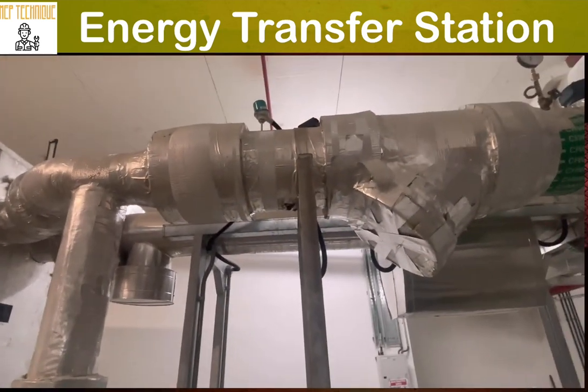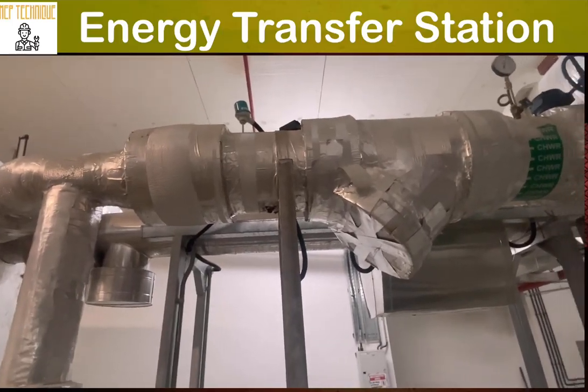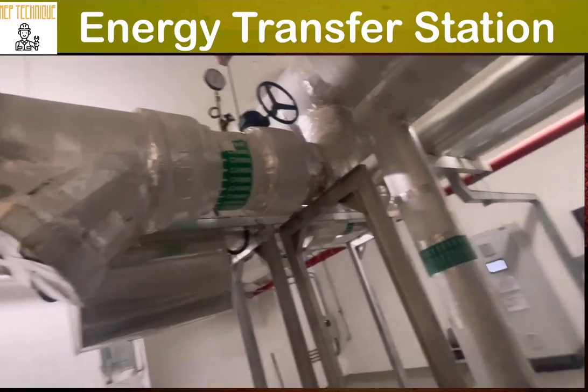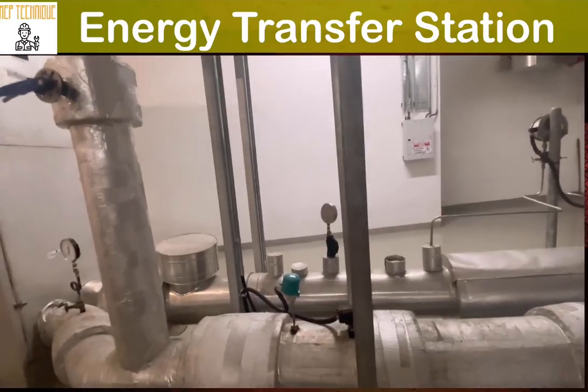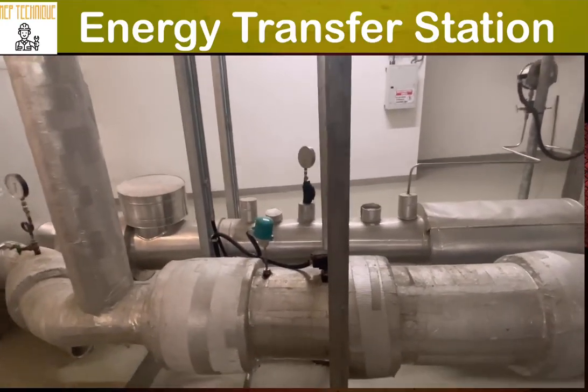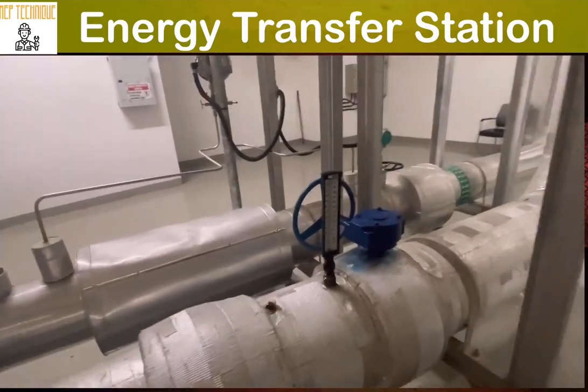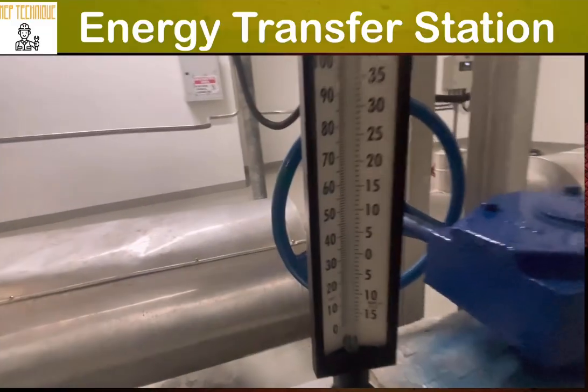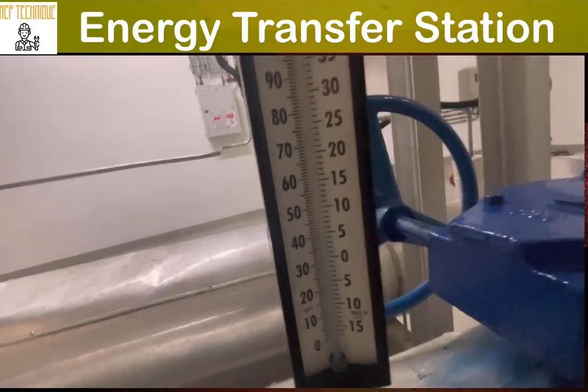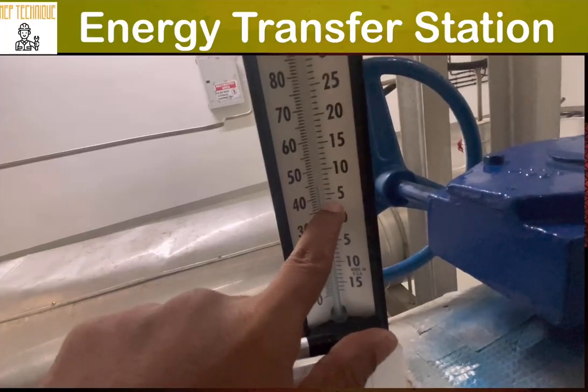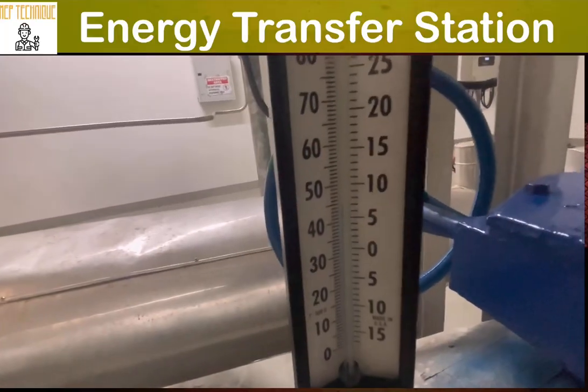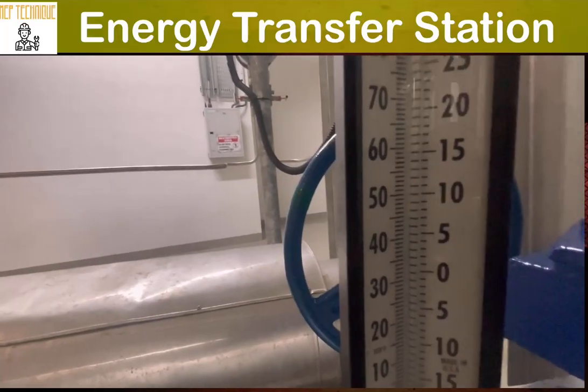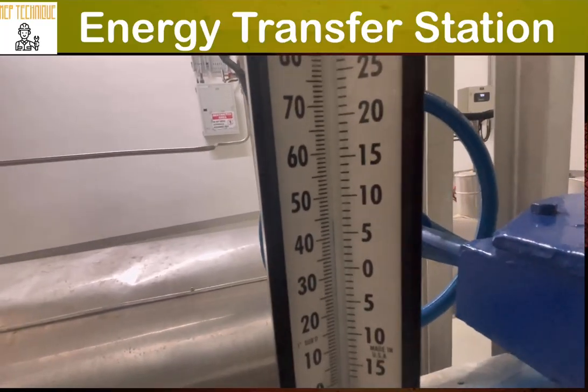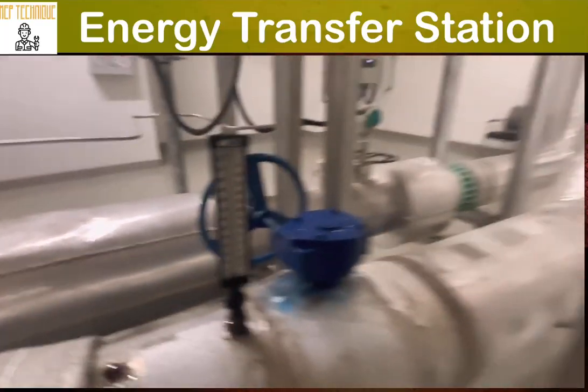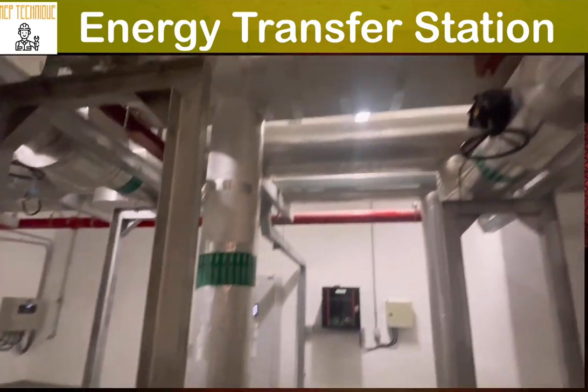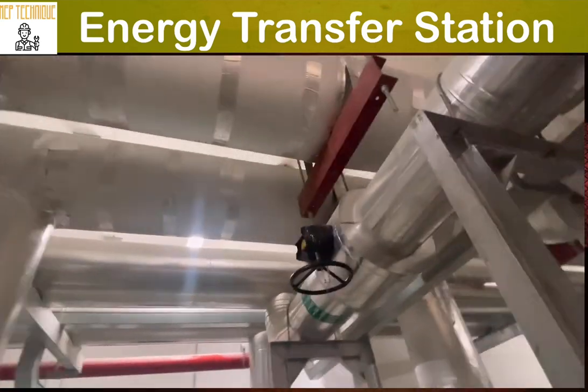Here you can see the temperature transmitter, pressure gauge and temperature gauge. Also in the building supply line, you can see there is a pressure transmitter and also a temperature gauge. Here you can see the temperature from the building is slightly higher than the temperature of the distribution company. It's showing 5, 6, 7 degrees Celsius, whereas our distribution company temperature was only 4.4 degrees Celsius.